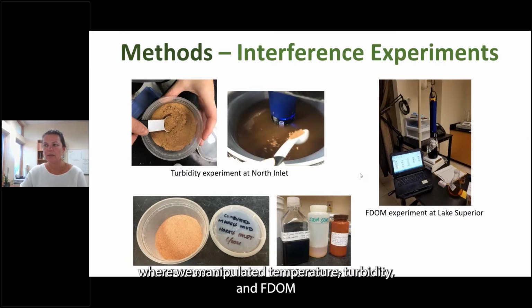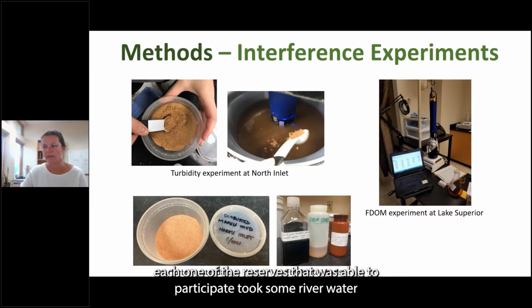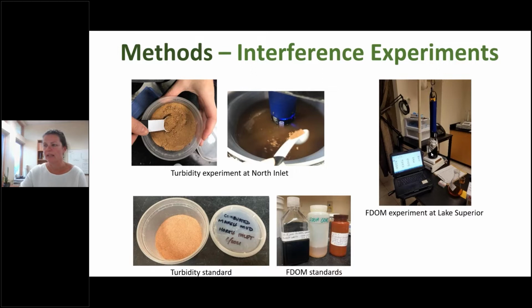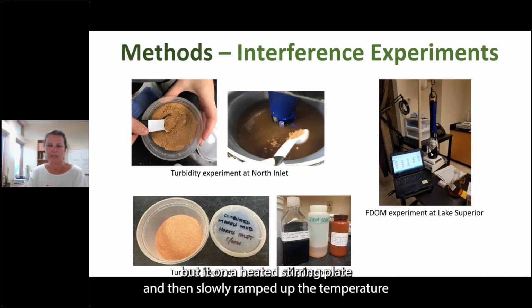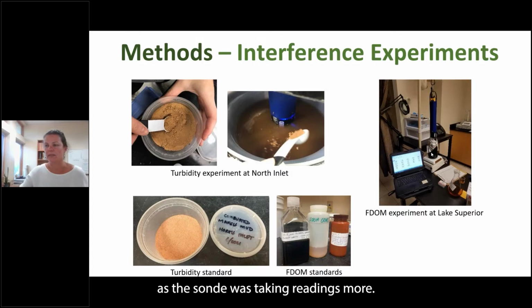So we did experiments in the lab where we manipulated temperature, turbidity, and FDOM in a beaker, basically with the sonde in it running. We added a standard turbidity mixture, which was basically combusted marsh mud from North Inlet. And then for the FDOM experiments, each one of the reserves that was able to participate took some river water and concentrated that down to about 5 to 10 times to come up with this standard that they slowly added to this stirring beaker as the sonde was reading both turbidity and chlorophyll. And then I don't have a picture for temperature, but basically we cooled down the sample, put it on a heated stirring plate, and then slowly ramped up the temperature as the sonde was taking readings.